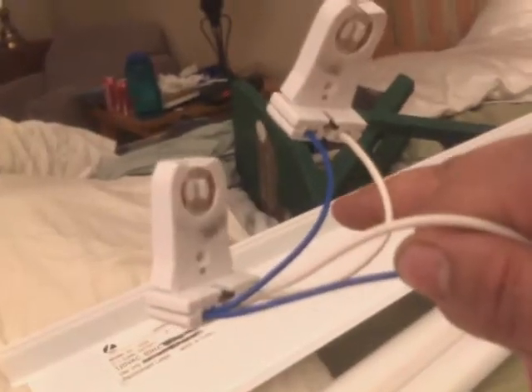Over here on the yellow wire side, you have the two yellow wires. These provide the filament heating voltage to the other side. So you have two wires coming here — I have a white one and a blue one because they were the ones inside the fixture. On the yellow end side, it's just a simple parallel circuit that heats the filaments on the other side.